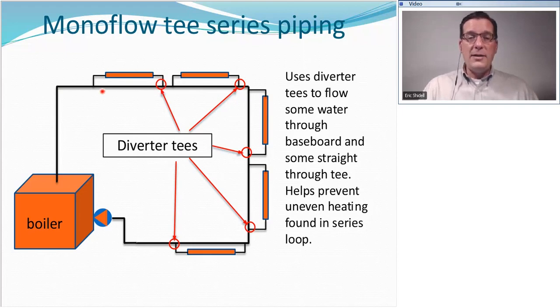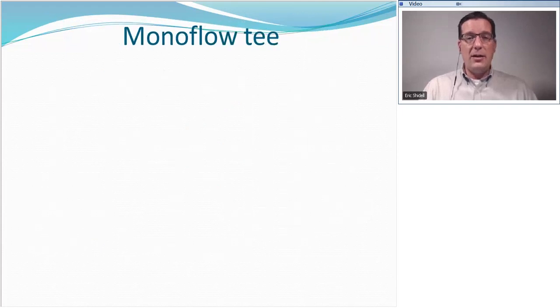What is going to cause water to want to take this long way around to go out of the main, back through the baseboard, and back into the main? And that device is called a diverter T. And the diverter T is the heart of the monoflow system. Here's what they look like on the inside.